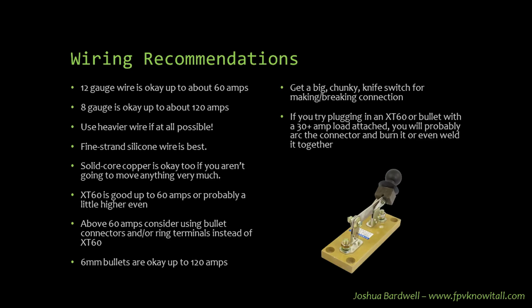Here are some general recommendations for wiring. In my experience doing battery testing, I built my current battery test rig with 12 gauge wire, and I do 60 amp discharges, for 2 hours at a time—obviously not continuously, but one battery after another. The wire got warm, and the XT60 connectors definitely got warm, but it never got to the point of being in danger of melting something or starting a fire. It wasn't even really painful to touch. So although an ampacity chart will tell you 60 amps is way too much for 12 gauge wire, those charts are really conservative.